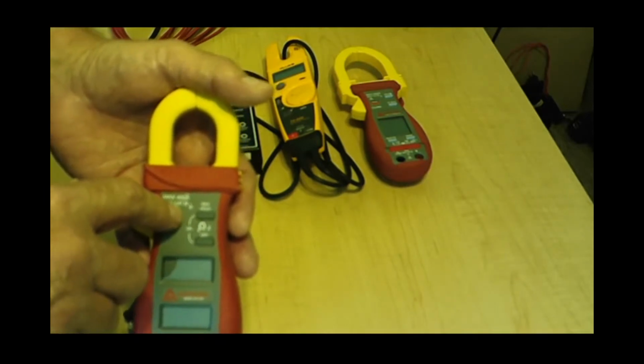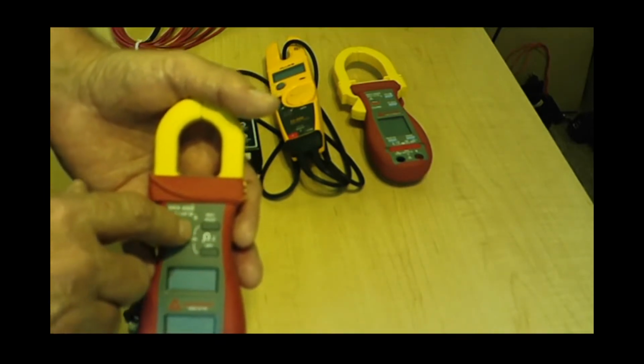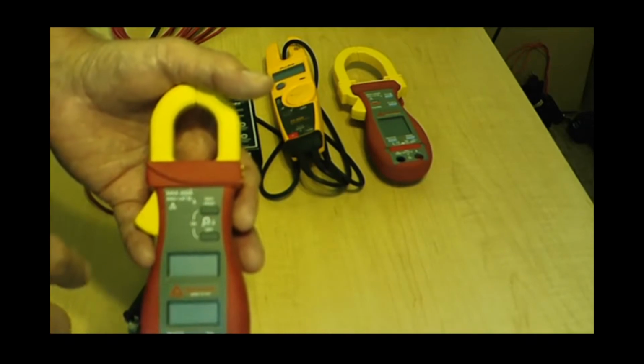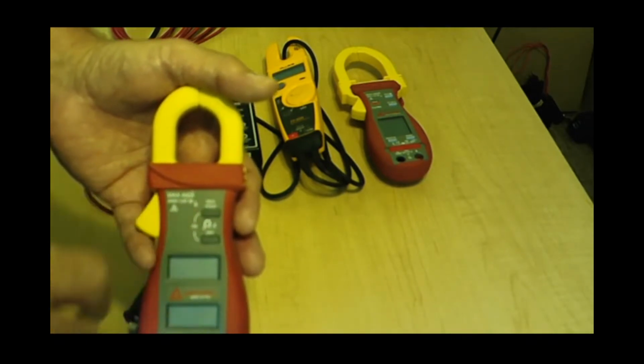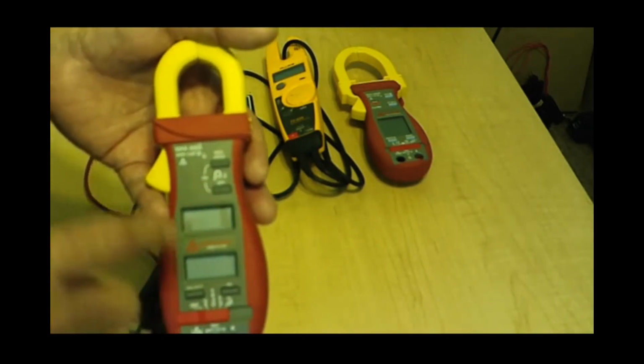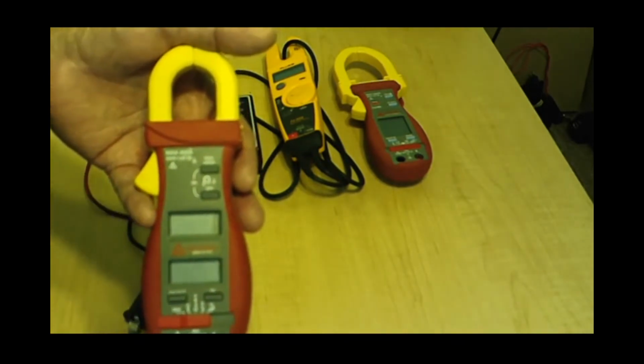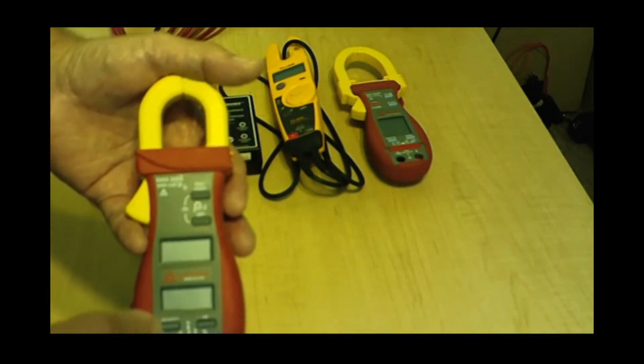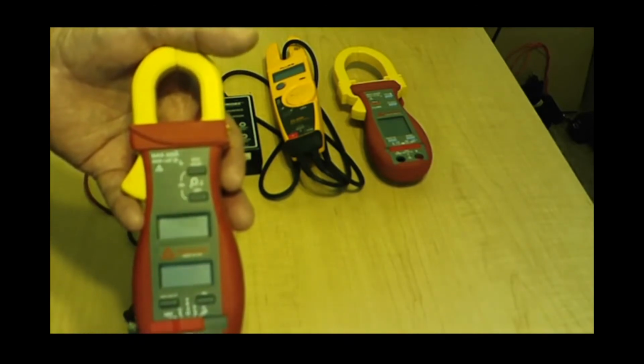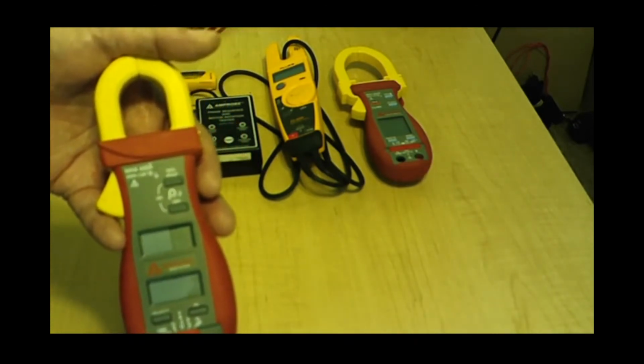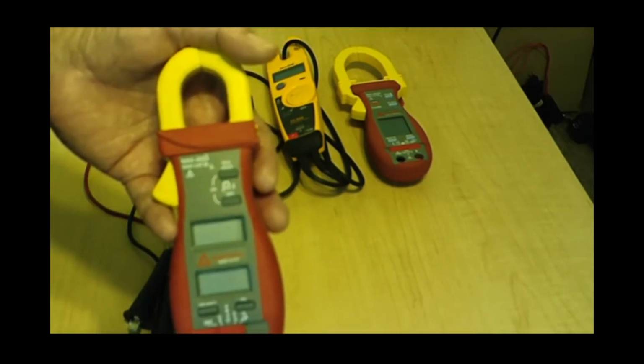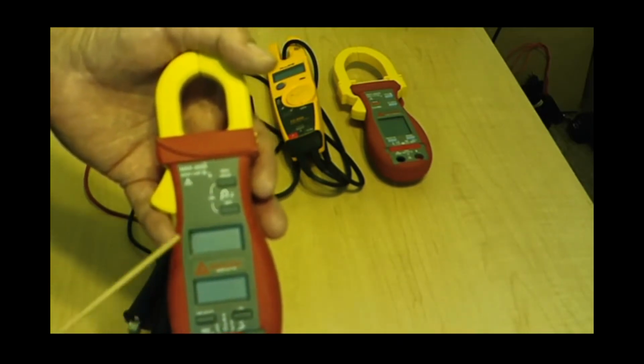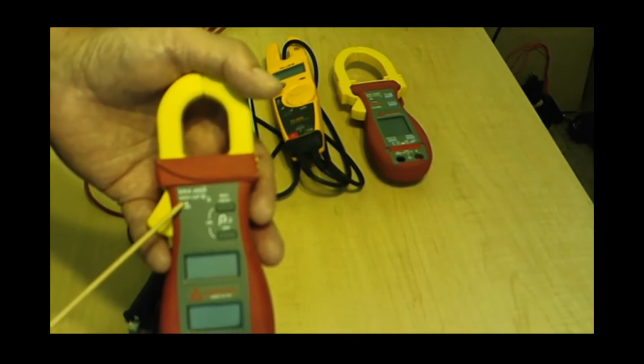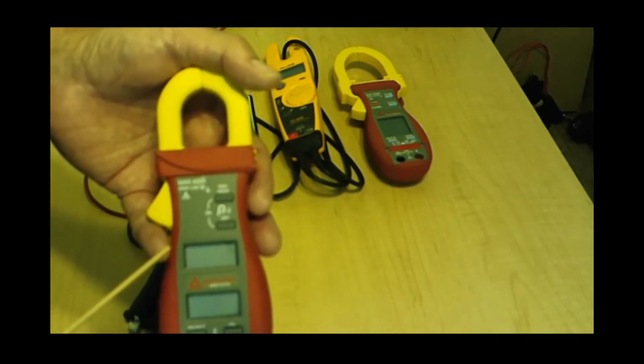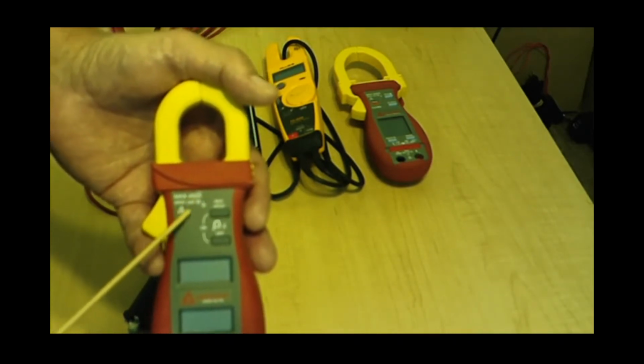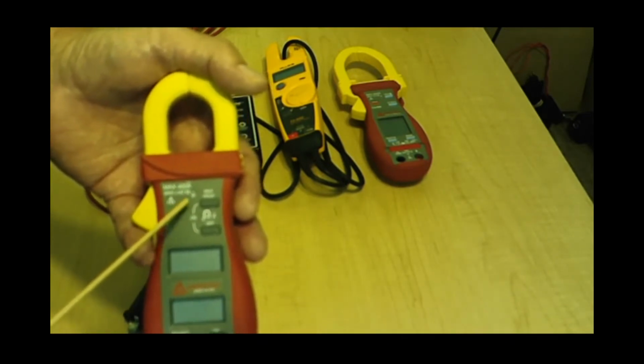Now, the category, one meter was category 3, the other one's category 2, this one's category 3. The category identifies the location of use. You could use this meter, and it will not explode from random transient voltages. Transient voltages occur many times a day in a facility. It's up to 300 times easily. And that high voltage spike could exceed the 600 volts, exceed the 400 amps. So the category is a safety protection telling you where you can safely use the meters.